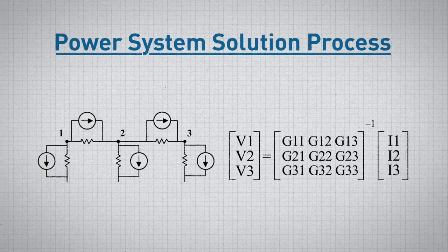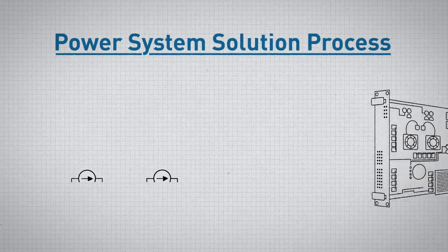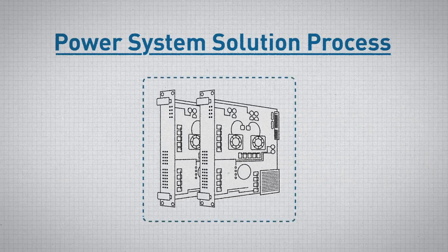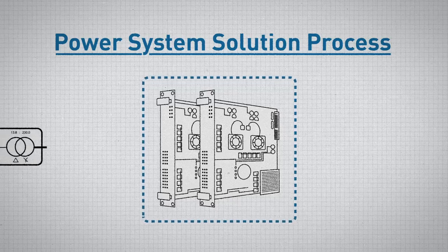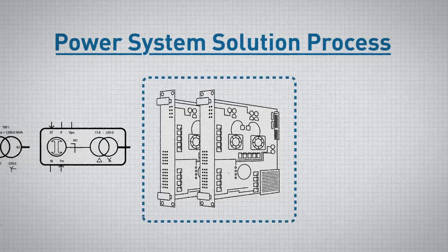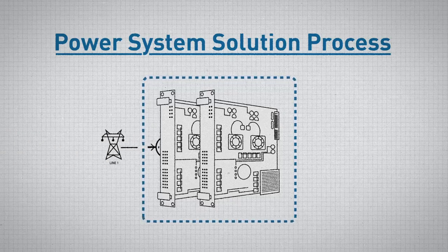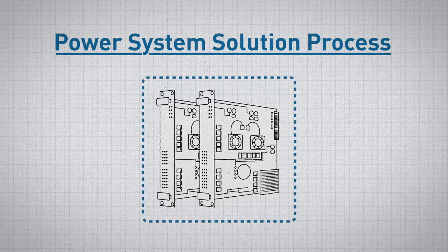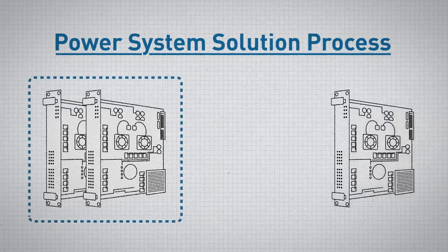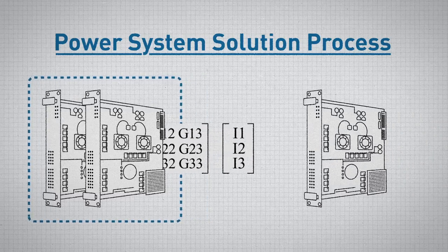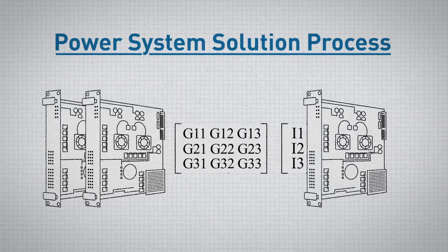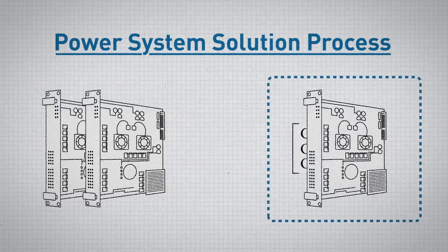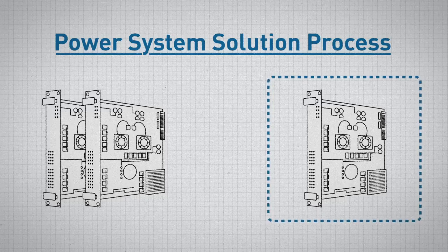The RTDS simulator's processor cards then calculate the equivalent conductance and current contributions associated with each of the components in the user's network and send them to the network solution processor, which is then responsible for calculating the voltages for the network.